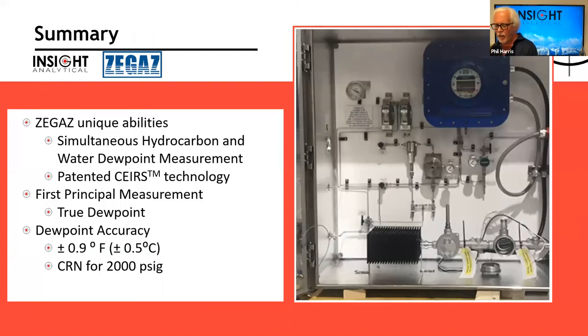Typical installation from us will look kind of like this. This is in a stainless steel cabinet. Heater at the bottom, deal with those Canadian winters, flow meters for the bypass loop. And again, Nayef, one of the things you were asking about was speed of response. Well, we do run a bypass flow on the coalescing filters, so we can increase that bypass flow. The analyzer itself doesn't need a lot of flow.